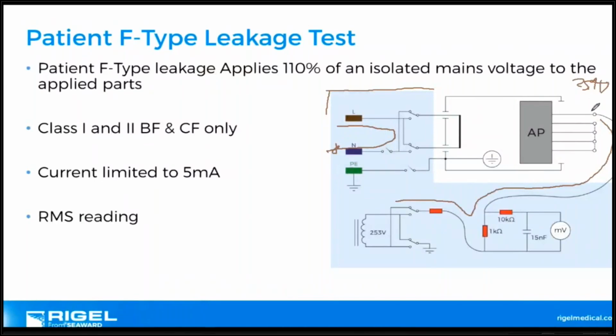But what we're trying to prove here by putting mains on the applied parts is that we have this isolation barrier between there and the protective earth, so that no current should flow. But current does flow because of the nature of conductors and insulators. So we've just proven that we have this isolation barrier. So that's the nature of the applied part, and that would be the guy or girl on the hospital bed who touches that hazardous voltage or current.